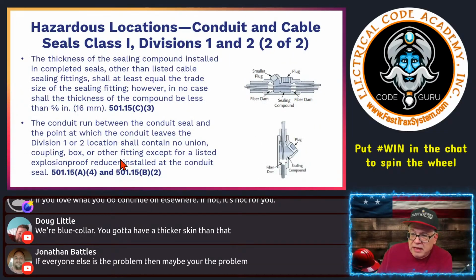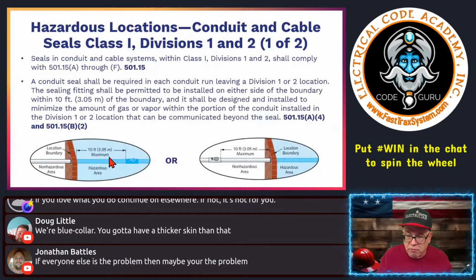In doing that, I can't have what? No unions, no couplings, a box, or other fittings except for a listed explosion-proof reducer installed at the conduit seal. So I may have a reducer on here for some reason in a transition. But other than that, nothing else between this seal right here and where it comes out. So nothing else in there. I cannot have anything else in there, like a coupling that could breach and breakdown or things like that.